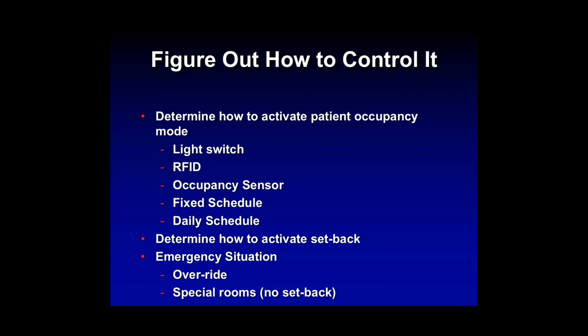And then on the occupancy sensors, as we did our investigation, we found that there are very few periods of time in the middle of the night that somebody's not in our ORs. We found that the terminal cleaning takes place in the middle of the night, that stocking by the anesthesia group takes place in the middle of the night, and then there's another stocking group that comes in and does the surgical supplies or the general supplies. So we saw at most a 3-hour period where there was nobody there.